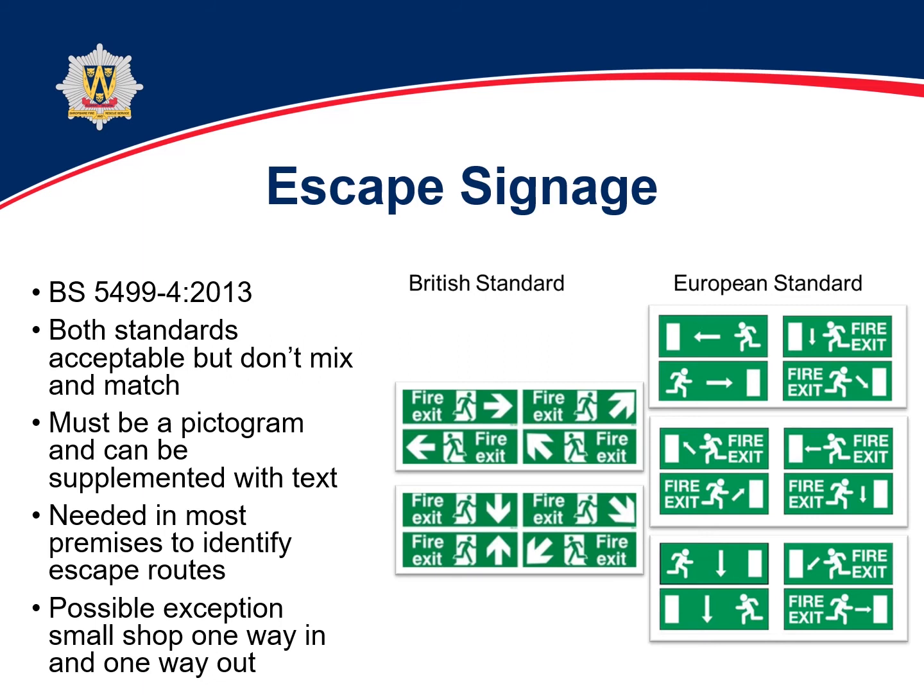Now the British standard has the running person in the door, and it has supplementary wording, and the European standard has the running person outside of the door. It may have the supplementary wording and it may not. Now both standards are acceptable, but what we say is don't mix and match. Okay, have one standard and stick to that.